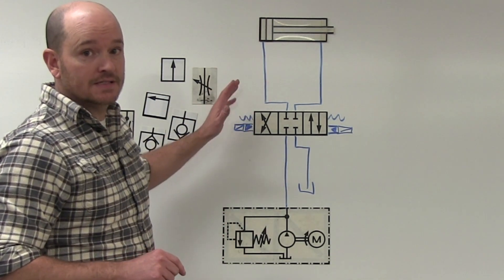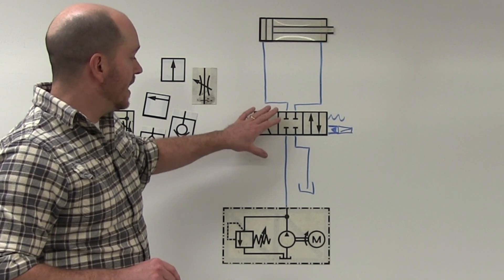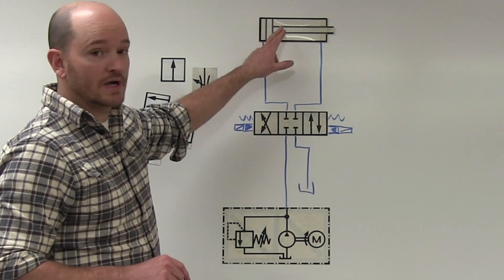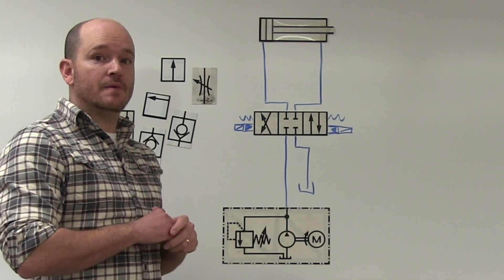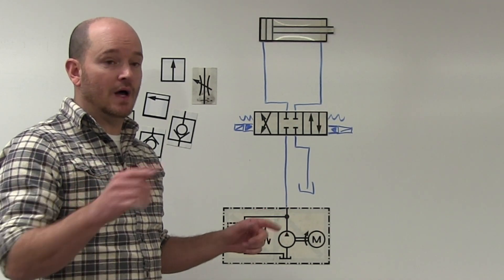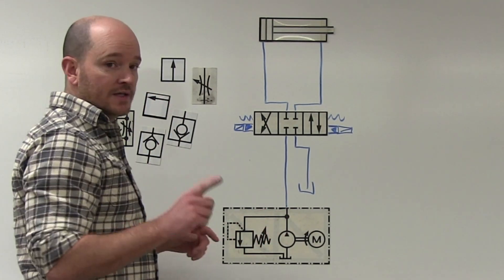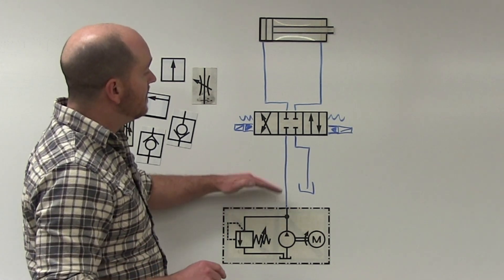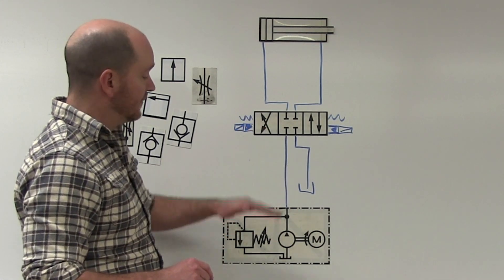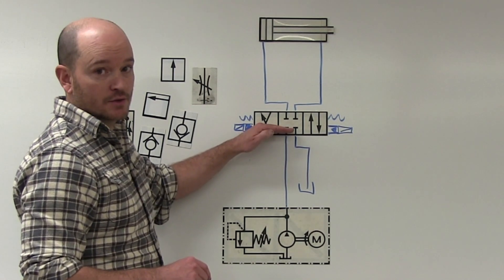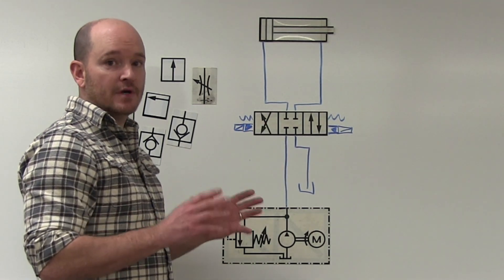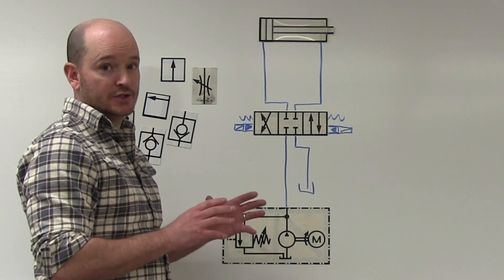Here I have a very basic fluid power hydraulic 4-3 directional control valve controlling a cylinder. Everything that I'm going to talk about here would remain perfectly true for pneumatics as well. So if I'm going to put a device before my directional control valve, so that's between my power source and my directional control valve, I do not require a bypass check valve.